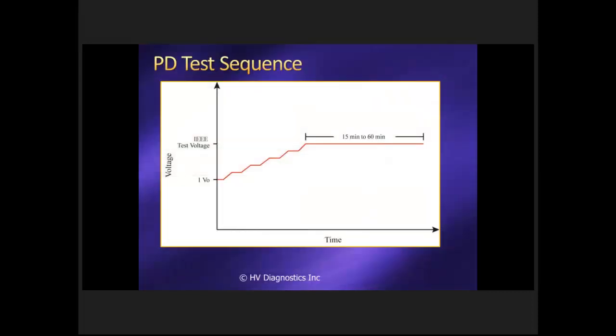Alright, if we do a PD test sequence, this is typically how we train people to do it. We start off with operating voltage and we step up the voltage in gradual steps, looking for PD. If we see PD, we capture it. If we don't, we just keep moving on, and we end up at the IEEE test voltage. If you want to do a combination, we combine it with a withstand test to make an intelligent withstand test, and we just need the PD monitoring during this whole process. So really, this is a PD measurement, and so is this, but this is also a withstand test on the cable. You'll see a bit later why that can be important as well.